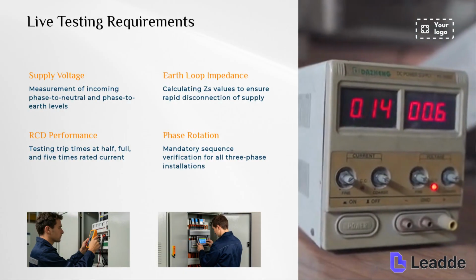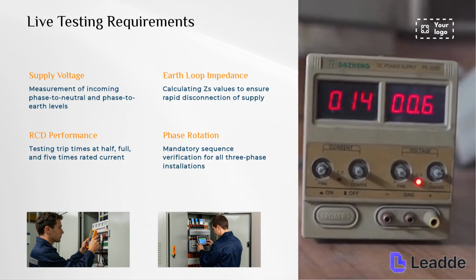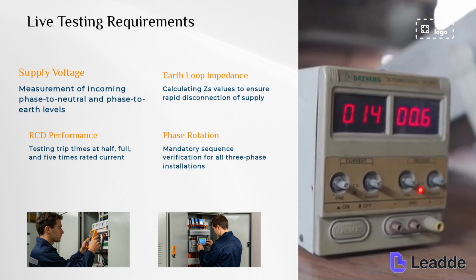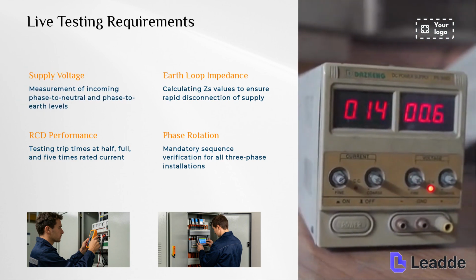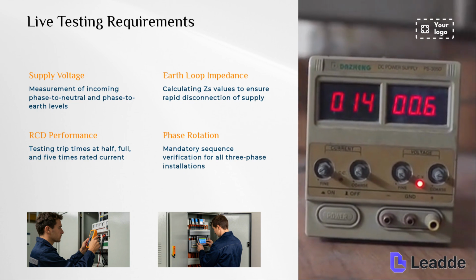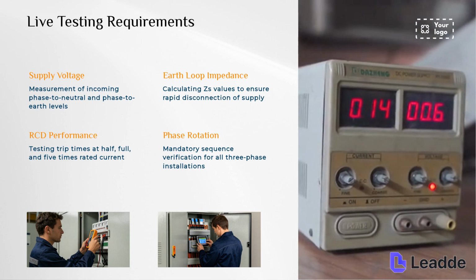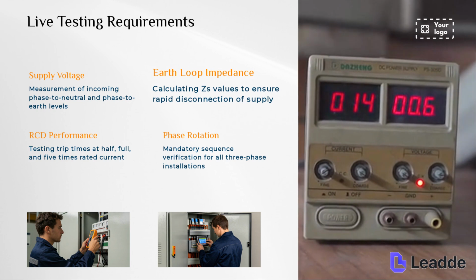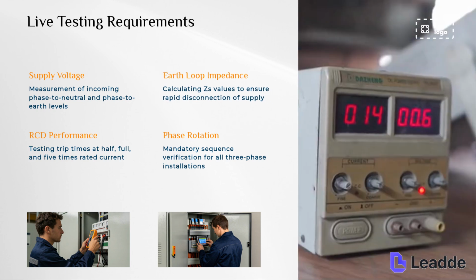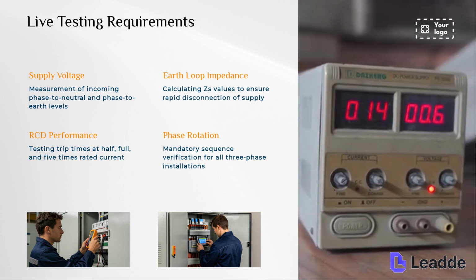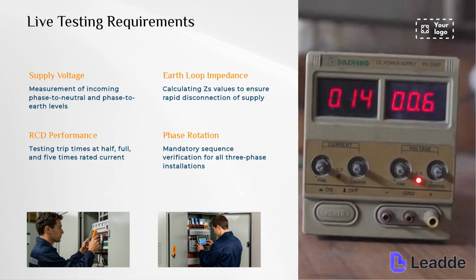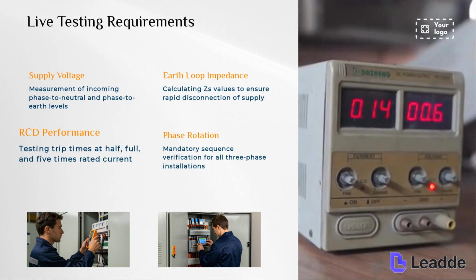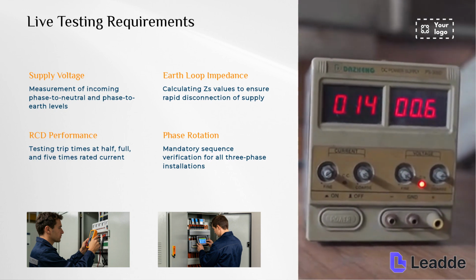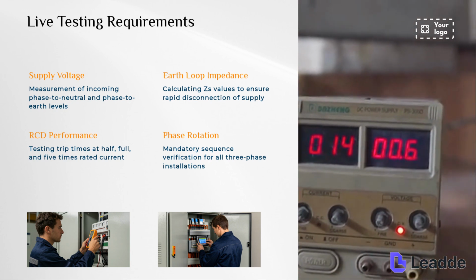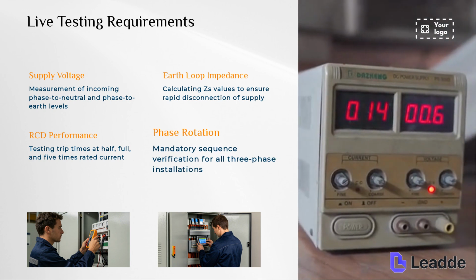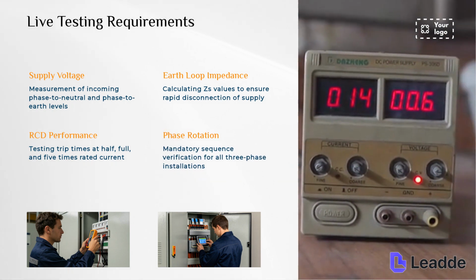Moving on to live testing requirements, it is necessary to measure the incoming supply voltage, specifically phase to neutral and phase to earth levels. We must also calculate earth loop impedance, known as Zs values, to ensure the rapid disconnection of supply during a fault. The performance of residual current devices, or RCDs, must be verified by testing trip times at half, full, and 5 times the rated current. For all three-phase installations, a mandatory phase rotation sequence verification is also required.